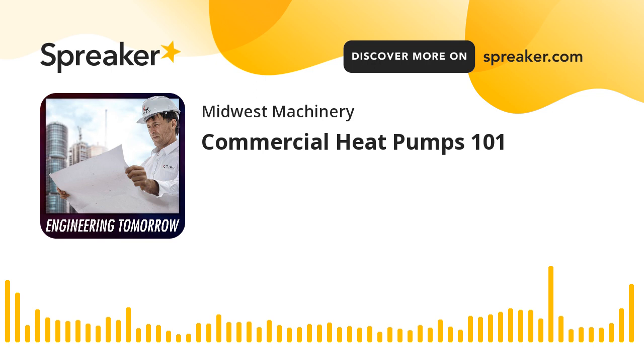Oh, okay. Tell me about, do you ever have to drain the water in the loop, or how long does the water last within the system, or is it constantly draining and replacing? On the cooling tower side, it's constantly being evaporated, so you need to treat that just like you would any cooling tower project. You're going to have to blow down because you're going to have a buildup of deposits and minerals in the water. On the loop side, it's a closed loop. So unless you have a leak, you shouldn't have to make up that water very often.